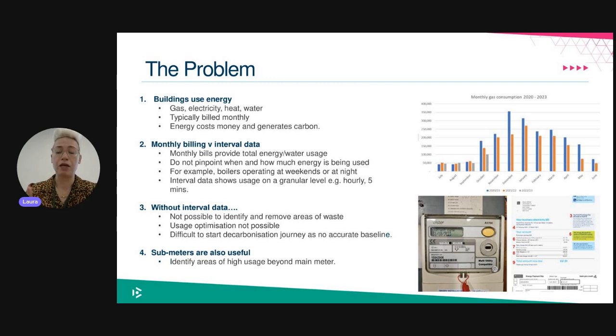I've got a good example at the moment, a very large college. They have 1 electricity meter, which is measuring all their imported electricity. They get an electricity bill based on that, and we have half-hourly data. However, it shows that at weekends, when the college is shut, they are still consuming half as much electricity as on a normal weekday. Nobody knows why. So we're working with them now to identify circuits that we can submeter and work out which circuits are being consumed. So are all the chillers working, for example, on a weekend, and nobody knows? It's all that.